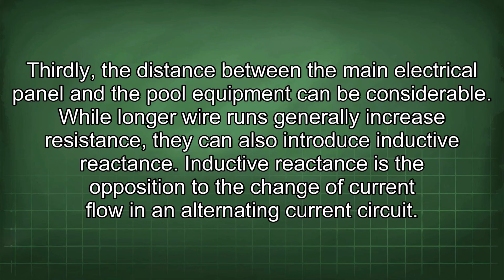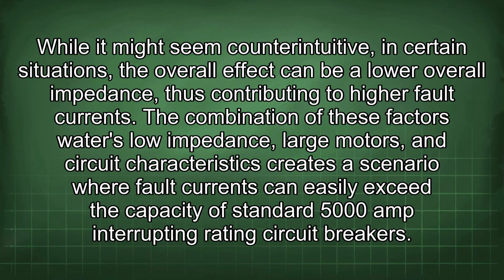Thirdly, the distance between the main electrical panel and the pool equipment can be considerable. While longer wire runs generally increase resistance, they can also introduce inductive reactance. Inductive reactance is the opposition to the change of current flow in an alternating current circuit. While it might seem counterintuitive in certain situations, the overall effect can be a lower overall impedance, thus contributing to higher fault currents. The combination of these factors, water's low impedance, large motors, and circuit characteristics creates a scenario where fault currents can easily exceed the capacity of standard 5,000 amp interrupting rating circuit breakers.